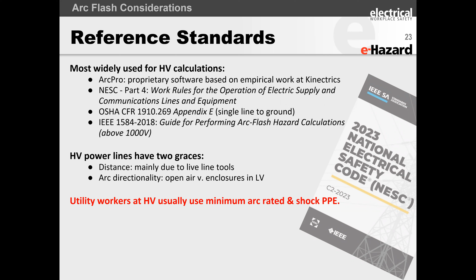But at high voltage, a lot of our safety rules are trying to get us away from that electrical induction, electrical shock, electrocution, okay? And that's where a lot of the emphasis is placed. And then you get the arc flash calculation. Obviously, these are two completely different hazards. But if you take that high voltage mentality and the way you work at high voltage and come into a low voltage environment, you're going to be protecting yourself against the wrong things. Similarly, if you're a low voltage expert and you get into a high voltage arena, you are going to be protecting yourself against the wrong thing.